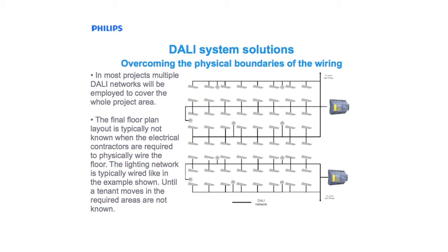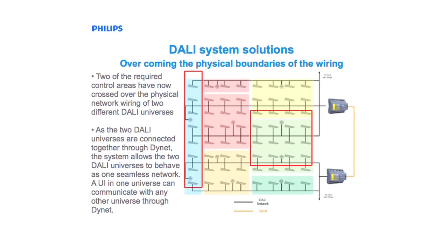This has left a physical gap between the 2 DALI universes. As the end user has taken occupation of the floor, the logical areas required have actually crossed the physical boundaries of the DALI network. To overcome these issues, the MultiMaster system can depend on the Dynet system. As the DBC120 DALI controllers are mounted and wired together using Dynet, the physical boundaries between the 2 DALI universes can be overcome, creating one seamless system.